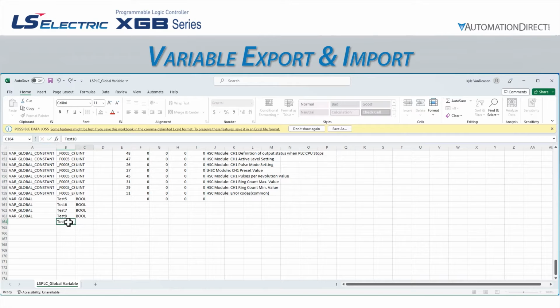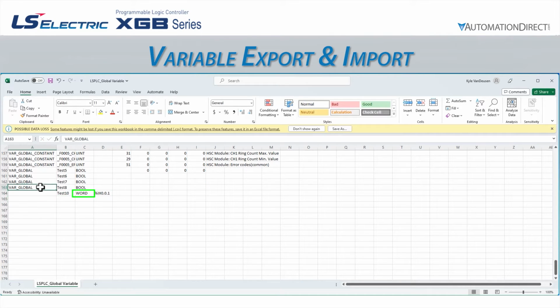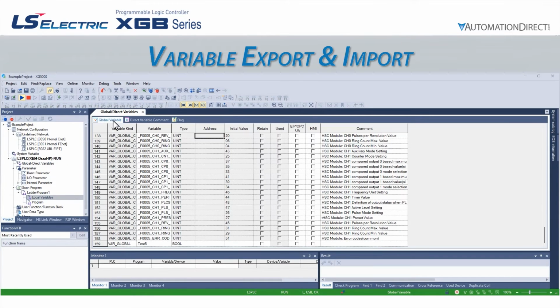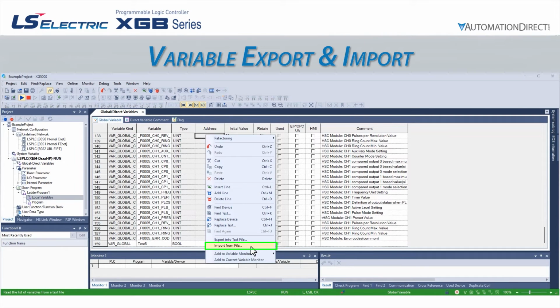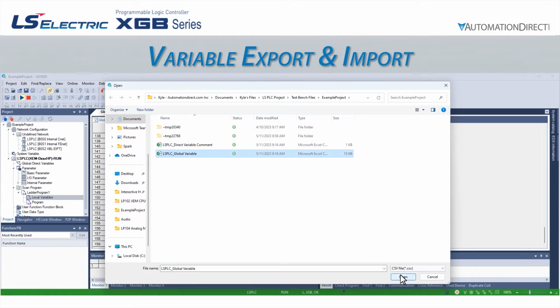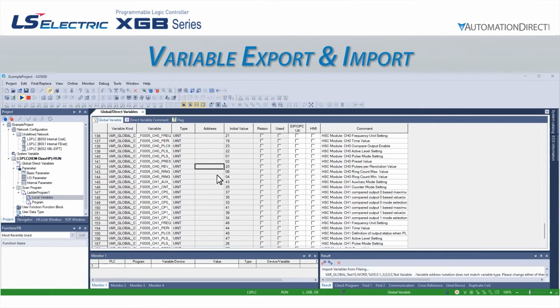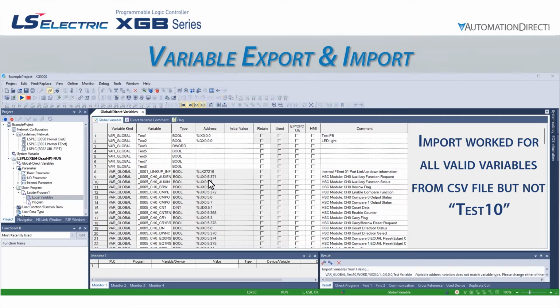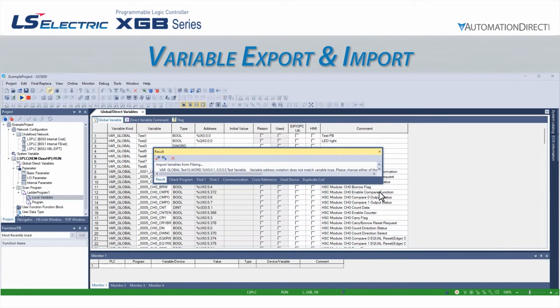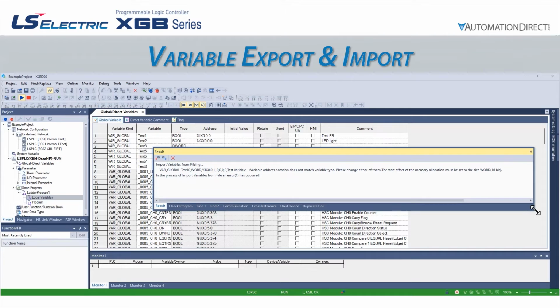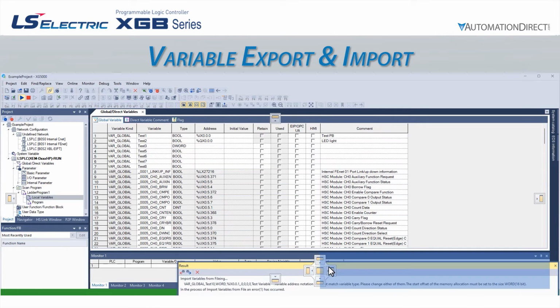Let's create a variable named test10 that lists the direct variable %ix0.0.1 in the address column, but we will put word into the type column. When we attempt to import, the software will give us an import error. This is because the direct variable %ix0.0.1 can only be a Boolean data type. The software import error will give us some indication of what is wrong with our CSV file to allow us to diagnose and fix the issue.